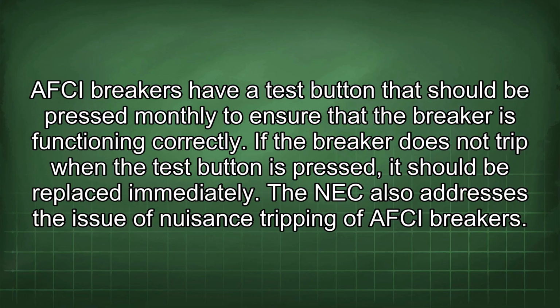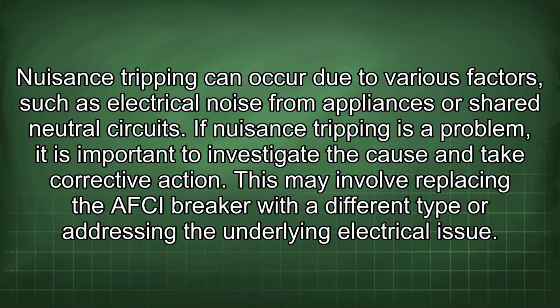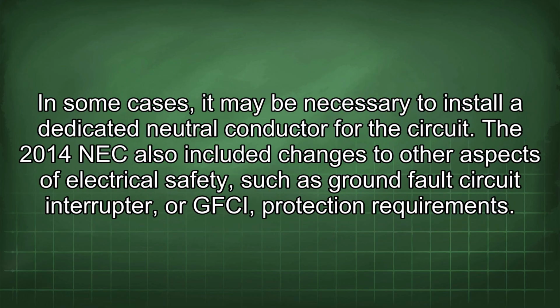The NEC also addresses the issue of nuisance tripping of AFCI breakers. Nuisance tripping can occur due to various factors, such as electrical noise from appliances or shared neutral circuits. If nuisance tripping is a problem, it is important to investigate the cause and take corrective action. This may involve replacing the AFCI breaker with a different type or addressing the underlying electrical issue. In some cases, it may be necessary to install a dedicated neutral conductor for the circuit.